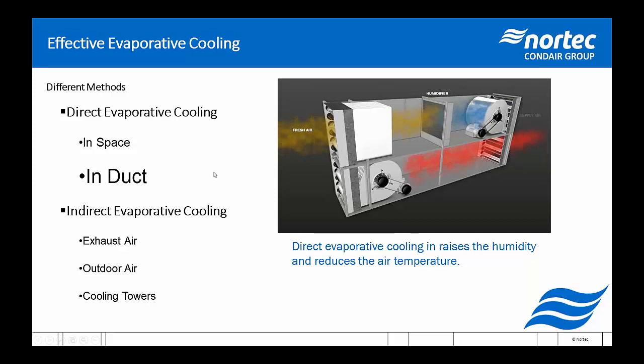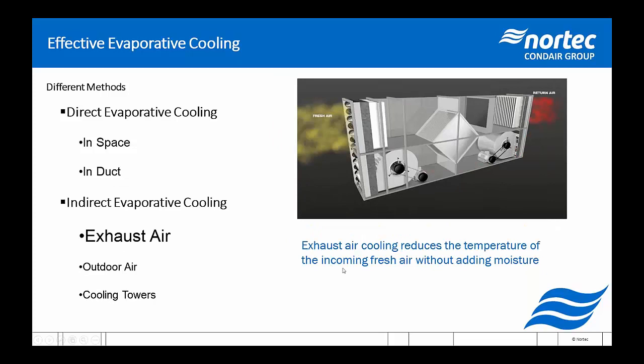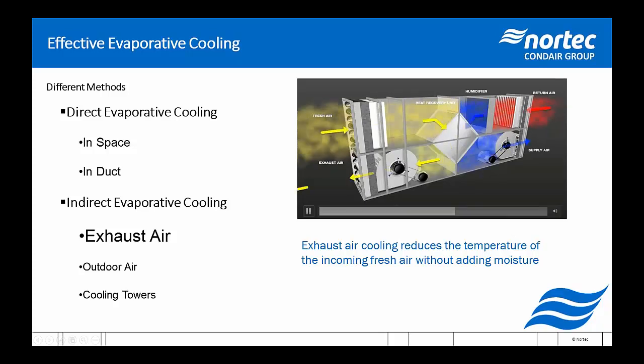On the indirect side, we've got cooling the exhaust air from the building. So this is actually incredibly common, especially in Germany right now, but we're starting to see it in North America, where the fresh air is coming through ideally a sensible heat exchanger before being put into the supply air. And we're taking our conditioned return air and saturating it. So we're making as big a difference on the sensible temperature side, the dry bulb side, as possible, allowing us to cool the fresh air as much as possible.